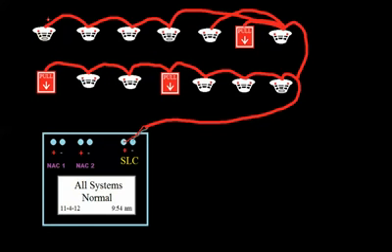So the way this works is, when I install new devices, I have to go into the panel and program these devices in. I have to tell the panel that these devices exist. So let's label these devices. Let's say that this heat detector, and I can tell it's a heat detector because you can see that little gray ring at the bottom, that indicates that it's a heat detector. Let's call that device 1. Then the smoke detector's 2, next smoke detector's 3, heat detector 4, 5, this is a pull station, 6, 7, etc. And then start over on the bottom, we go 8, 9, 10, etc.